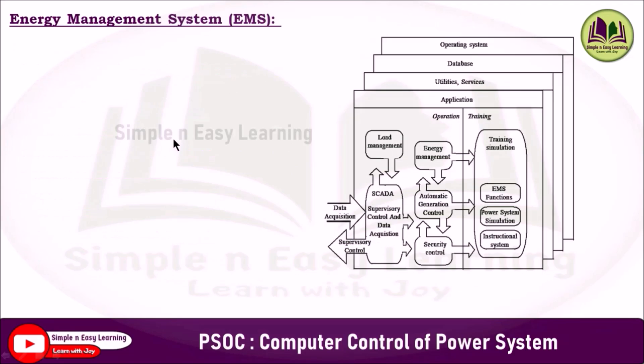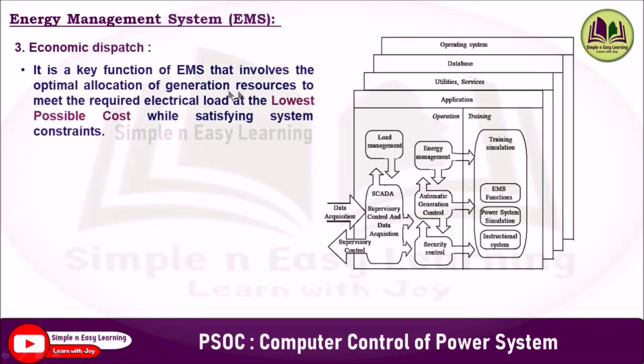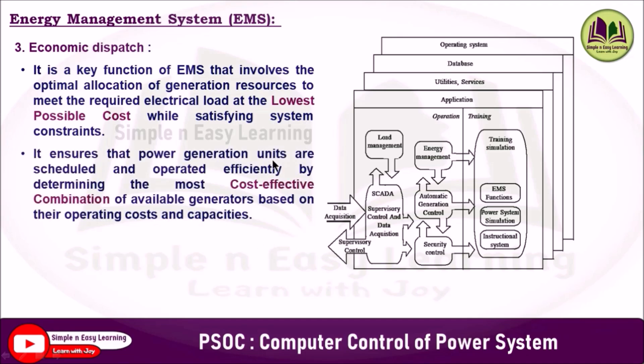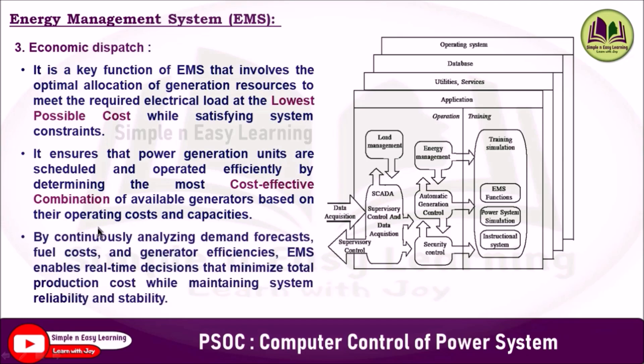The third function is economic dispatch. It is a key function of EMS that involves the optimal allocation of generation resources to meet the required electricity load at the lowest possible cost while satisfying system constraints. It ensures that power generation units are scheduled and operated efficiently by determining the most cost-effective combination of available generators based on their operating cost. By continuously analyzing demand forecasts, fuel costs, and generator efficiencies, EMS enables real-time decisions that minimize total production cost while maintaining system reliability and stability.